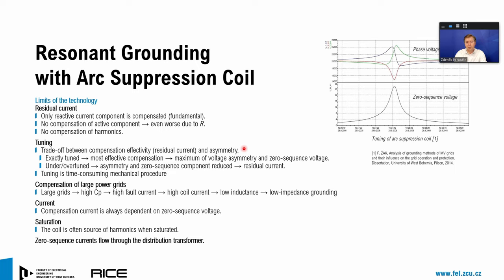The problem is also a complex tuning, which is not an easy task when tuning the arc suppression coil. The problem is also the compensation of large power grids, which leads to low impedance grounding, having several consequences within the protection of such a power grid. The compensation current, which is produced by the arc suppression coil, is always dependent on zero sequence voltage. The coil is often a source of harmonics when saturated, and there is one important drawback. The zero sequence current flows through the distribution transformer and loads it.